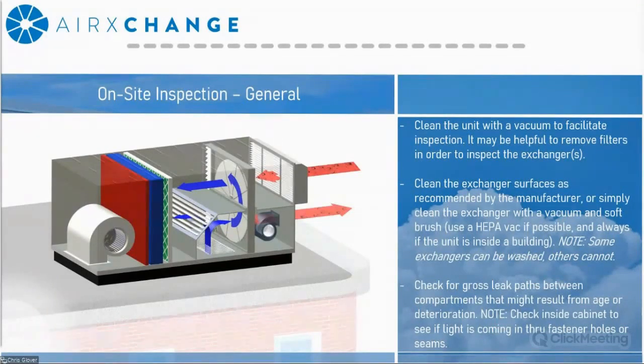After you're done cleaning, check for gross leakage paths or obstructions that would minimize the airflow being delivered by the system. The easiest way I can recommend doing this is to bring a flashlight and shine it in different sections of the cabinet. Really what you're looking to do is to see if there's any light penetrating. This could be through fasteners that have been removed, or maybe panels that have been removed over time due to servicing. Really any areas where gross air could recirculate back into the building.